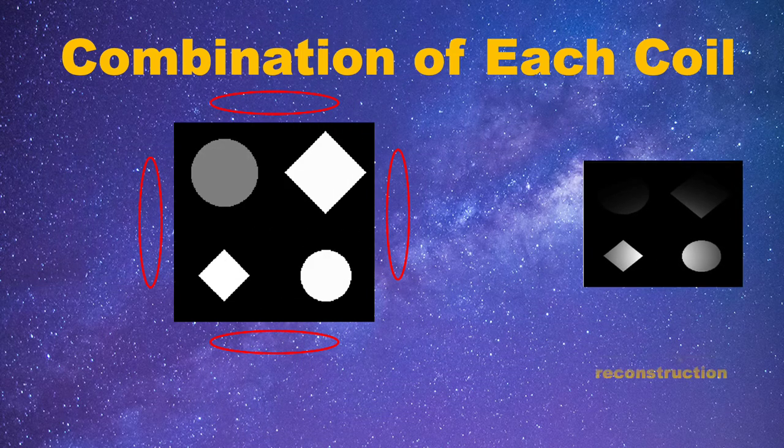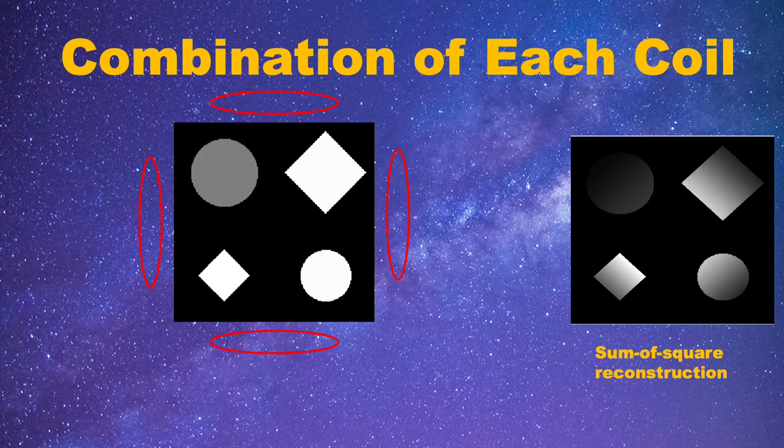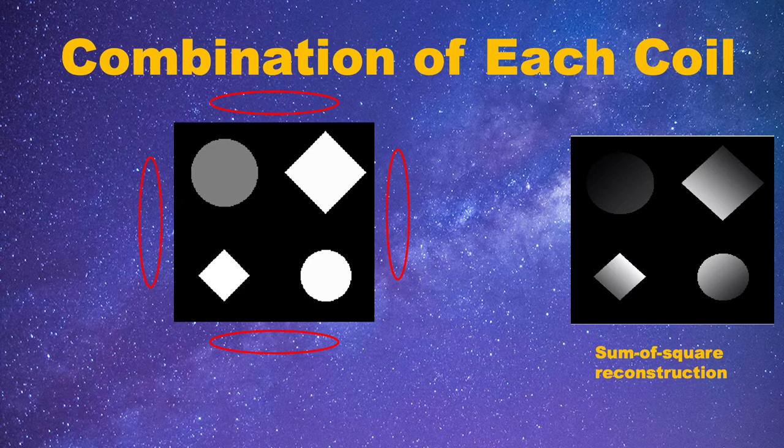Although each of the images show the complete object, we still want to combine them to get an image that better represent the object. There are many ways to do the combination. The easiest way is called sum of squares, which means adding together the squares of the coil images. This is a commonly used combination method in the real scanners.